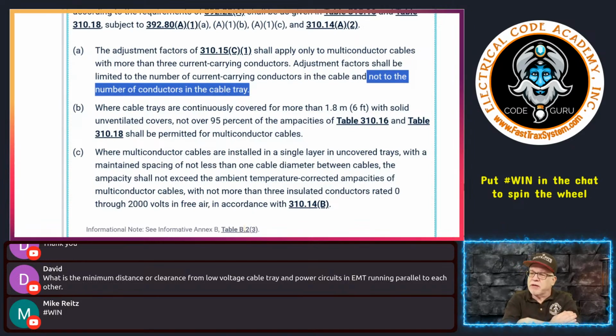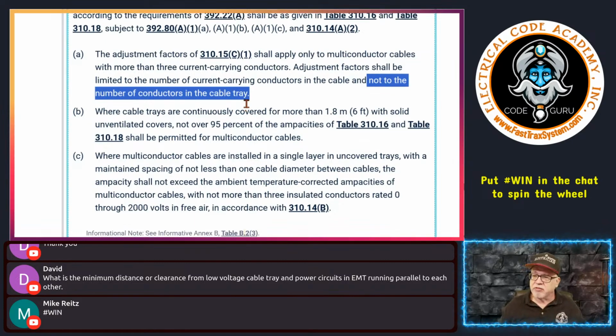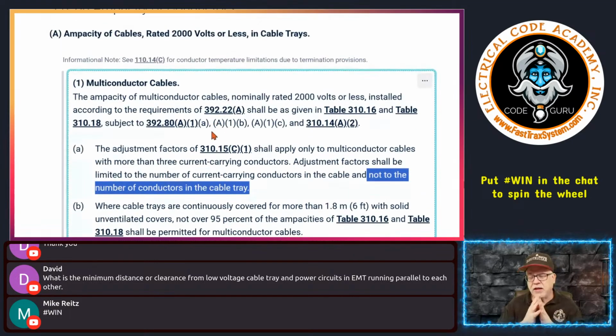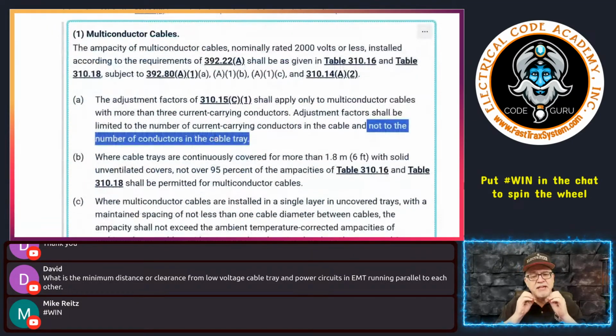And if I have multiple cables inside of this cable tray, and again, I'm meeting the requirements of 392.22(A) as far as how they go in there, right? If I meet that requirement, then it's saying, you know what? I don't have to take any consideration about the adjustment factors at all as long as my cables don't have more than 3 current carrying conductors in it, right? And the other thing to remember here is that this is, again, not applying to the number of cables itself inside of the cable tray.